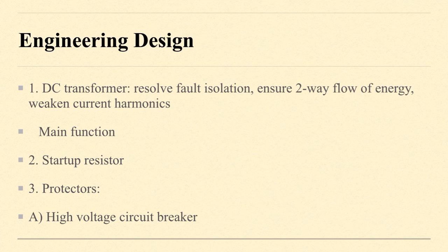First is DC transformer. Not only should DC-DC transformers resolve fault isolation and ensure two-way flow of energy, but current harmonics need to be weakened as well. In fact, we use transformers in MMC HVDC transmission systems, and its main functions include the following aspects: convert the voltage of AC systems to the secondary voltage matching with the DC side of the converter, and it can provide a portion of commutating reactance. It can isolate the zero sequence component generated by AC system asymmetry.